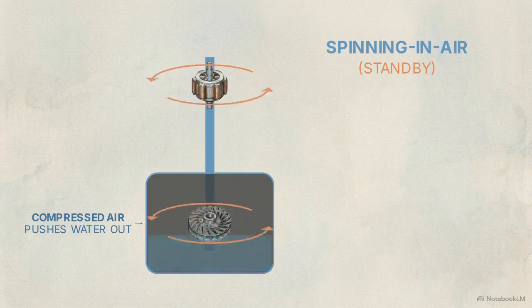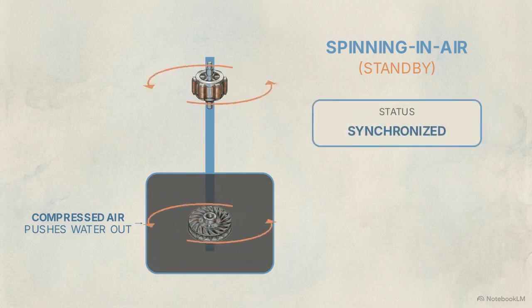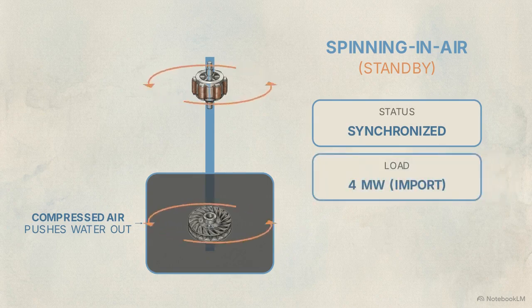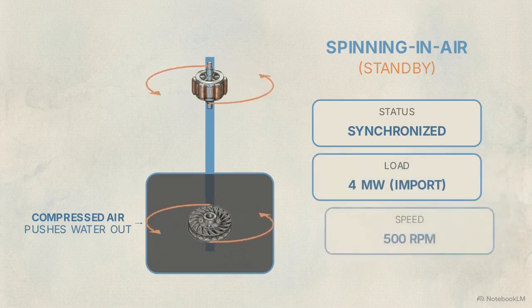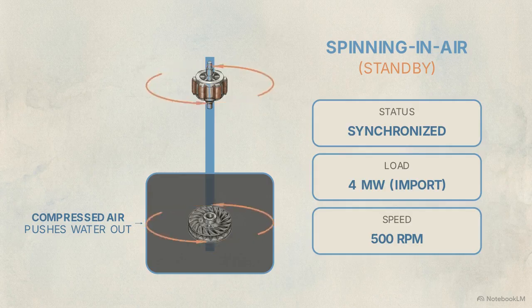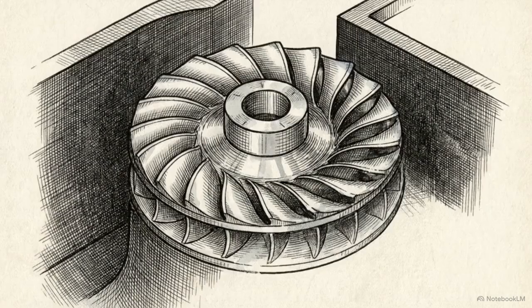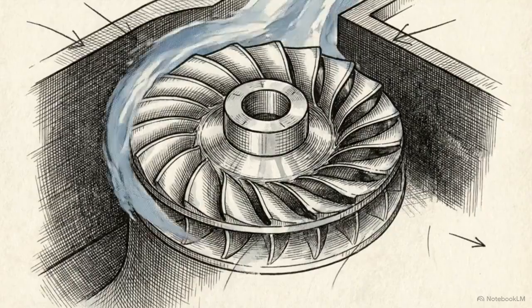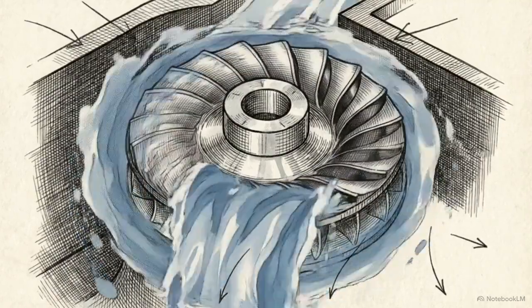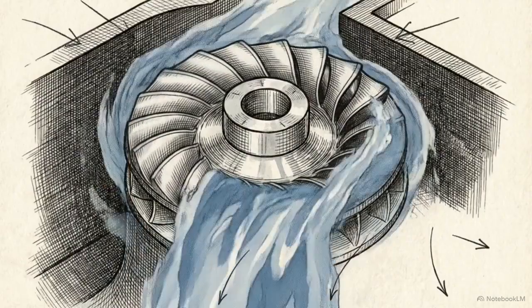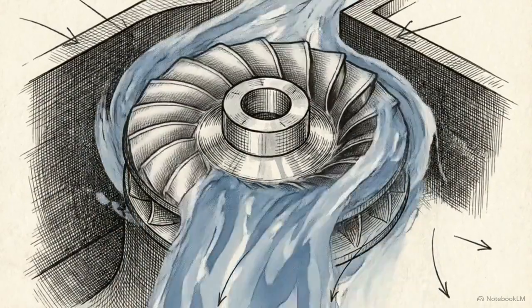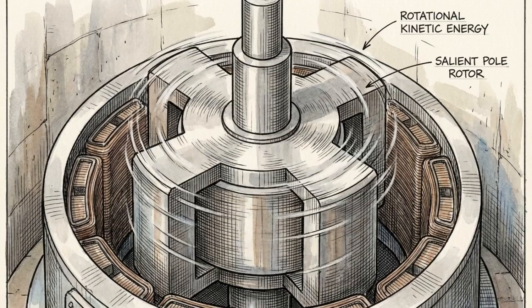Dinorwig bypasses this delay by holding the machines in a standby state known as spinning in air. The generator remains synchronized to the grid, drawing roughly 4 megawatts of power to keep the rotor spinning at a synchronous speed of 500 revolutions per minute. To accomplish this without damaging the equipment, high-pressure compressed air is continuously injected directly into the turbine casing, keeping it entirely clear of water. Removing the water eliminates hydraulic drag. The massive steel rotor spins freely, maintaining its synchronous speed without pulling an excessive load from the wider grid.